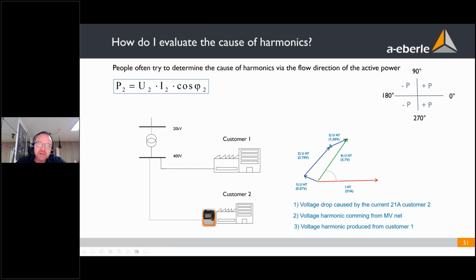And especially the disturbances out of the grid will change in amplitude and phase angle between daytime and nighttime. So it could be that this customer is producing 24 hours exactly the same, but the grid value is changing. And now your analyzer will tell you during the day you are positive, during the night you are negative. No, this customer is still doing the same. All other values will change whether it is positive or negative. So the direction of harmonics will not be possible. You can't use it if many customers could produce harmonics.